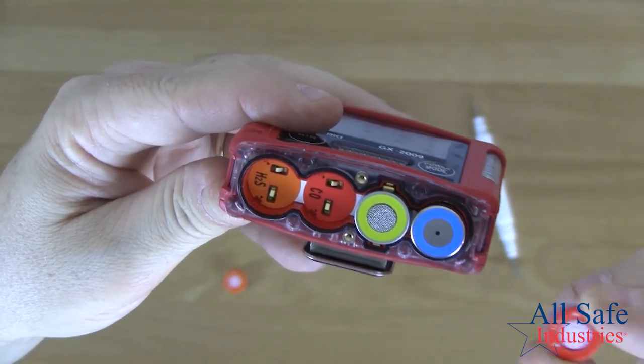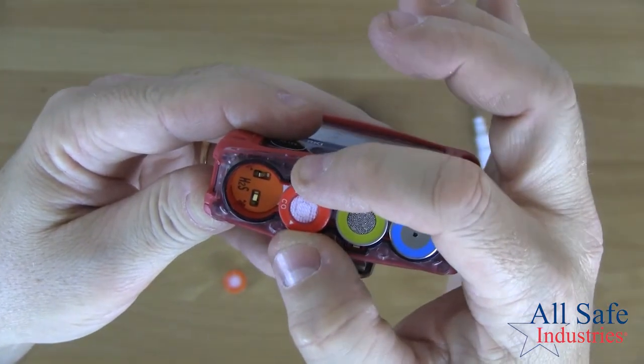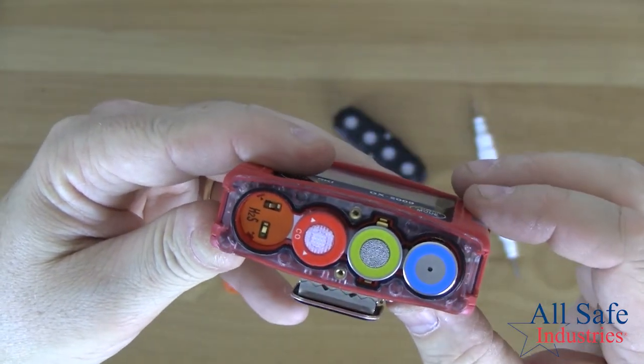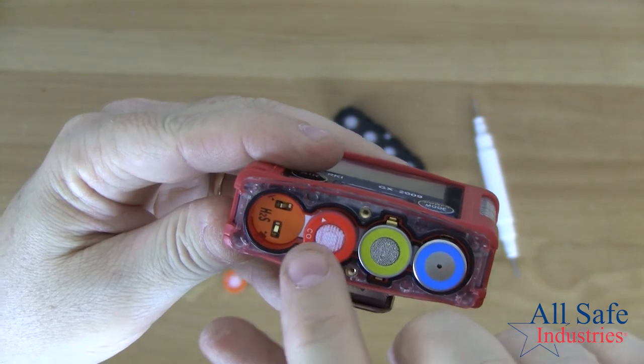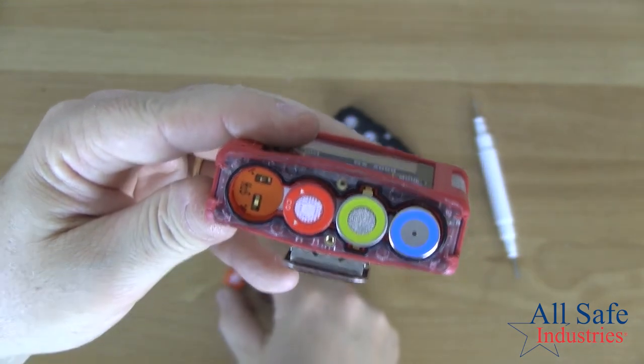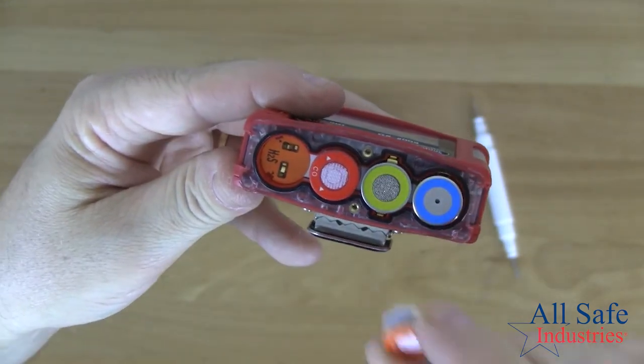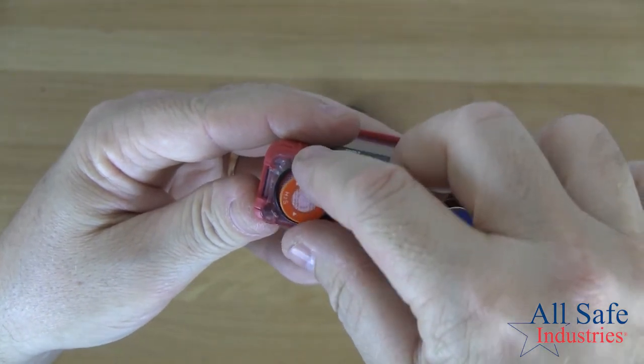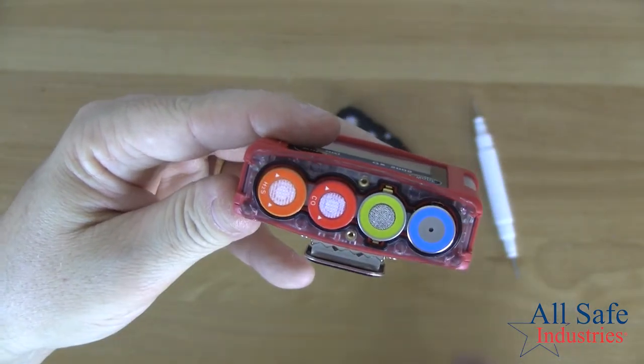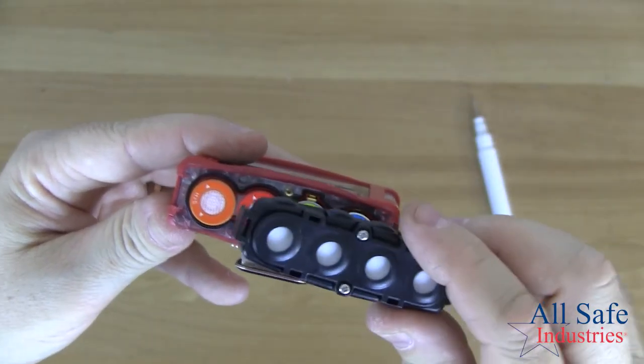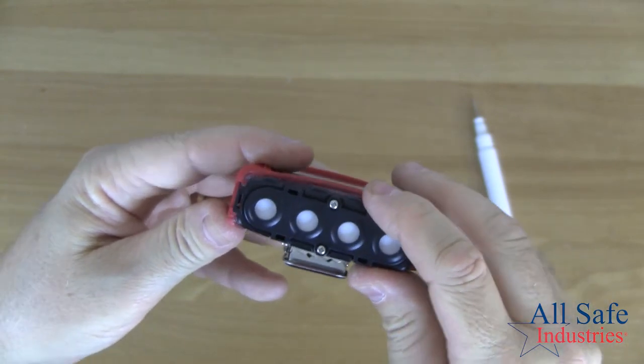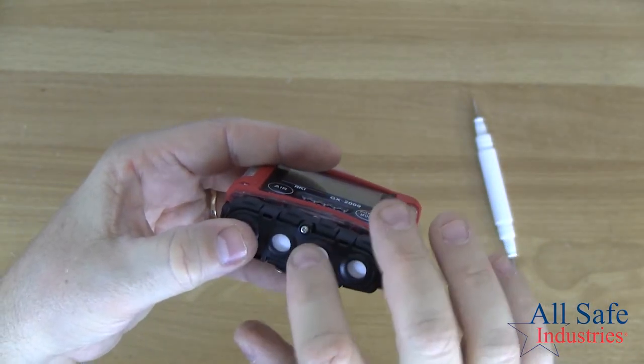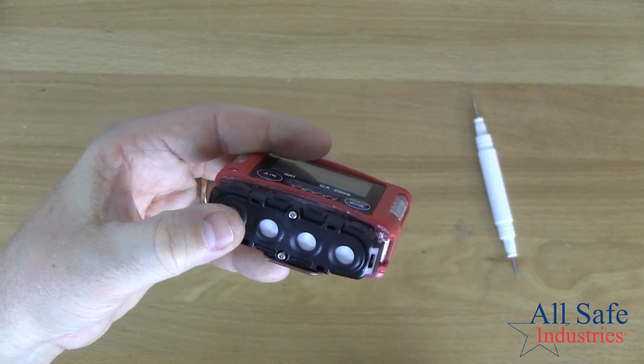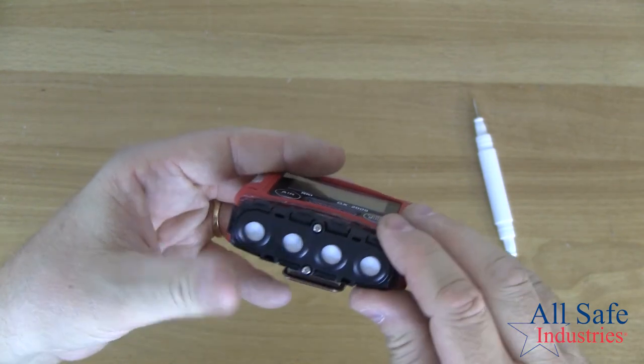Do you see those? And so we want to make sure that when we set that in there, those arrows line up, because that way we're lining up with the contact points inside the instrument. And so same thing with our new H2S sensor. We want to drop that in, and then of course we would reinstall our sensor cover, snap it all together, cinch down our screws, and that's how we change out the sensors. It really couldn't be easier.